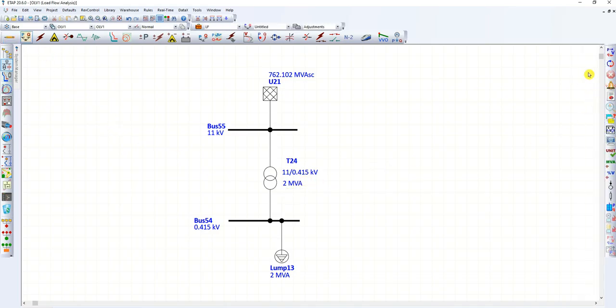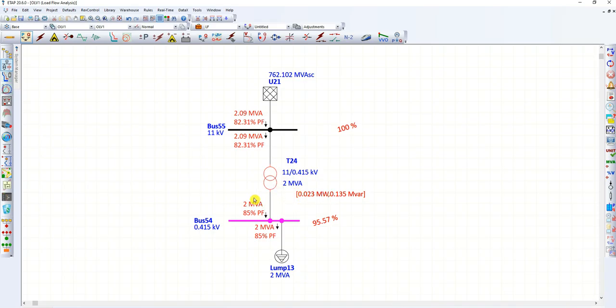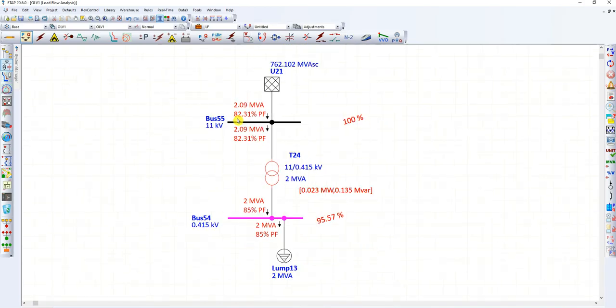Let's run this load flow. The red symbol means the transformer is overloaded. The transformer is overloaded — why? Because the transformer rating is 2 MVA, but it is drawing 2.09 MVA from the source side, because transformer losses are present.